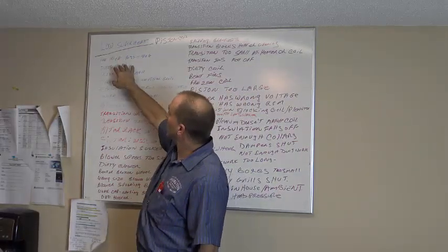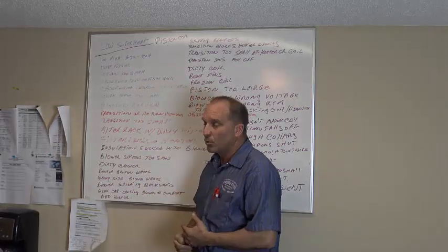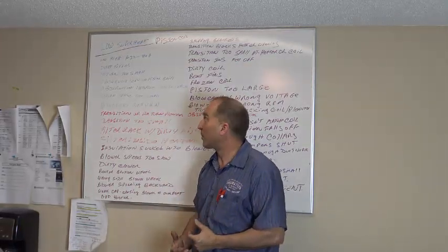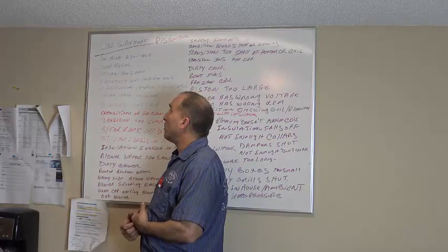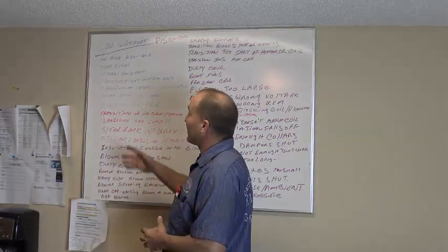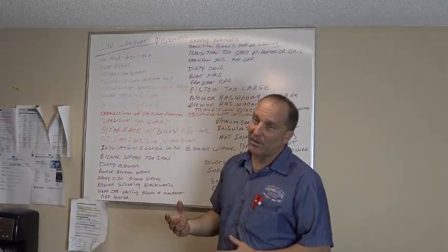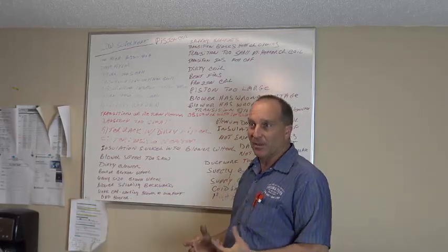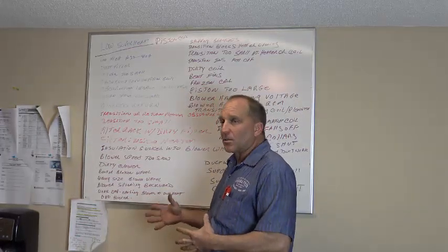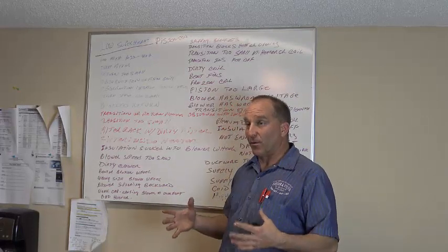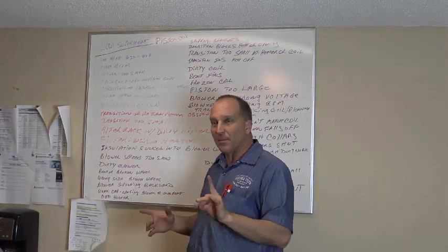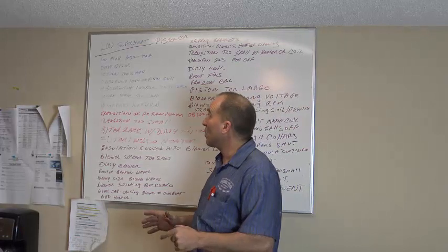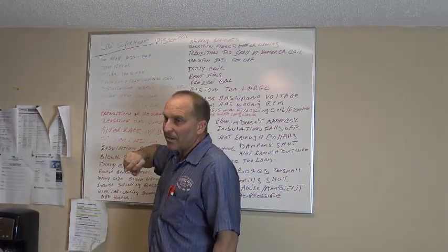First of all, if you have too much refrigerant in the system, that's going to give you a low superheat, because too much refrigerant running through that evaporator coil is not going to pick up the heat from the evaporator coil. If you have a dirty filter, it blocks airflow through the system. So when I say low superheat, a lot of times what you have to think about is what is going to cause low airflow through the system. You remember me telling you that? If anything causes low airflow or a blockage of airflow, that is going to cause a low superheat with a piston coil. Now we're going to get into expansion valves in a minute, but this is all with a piston coil. So if you got a dirty filter, it blocks the airflow through.